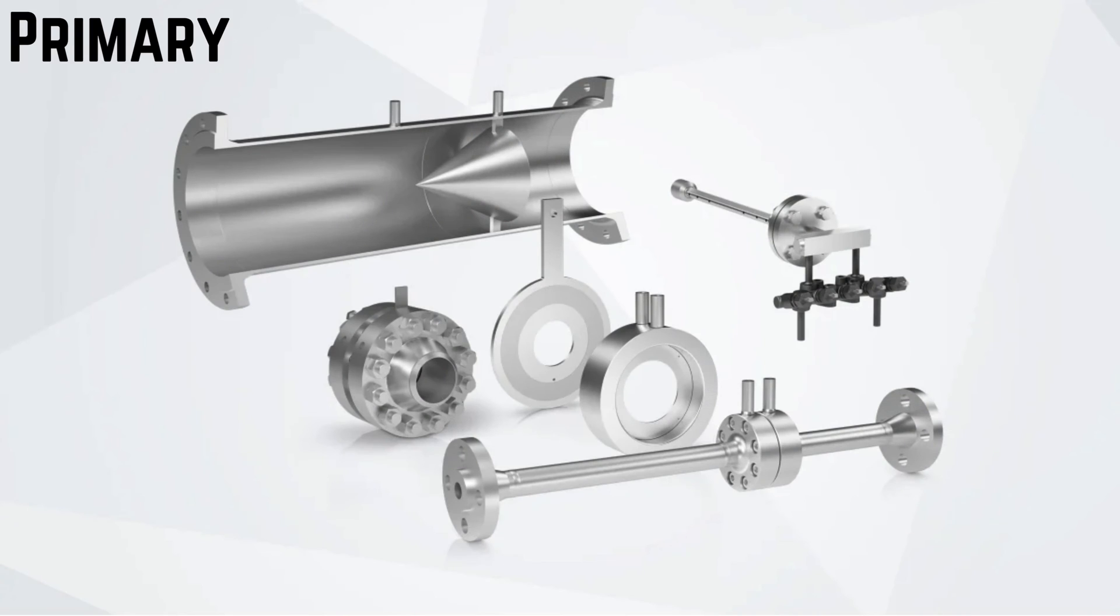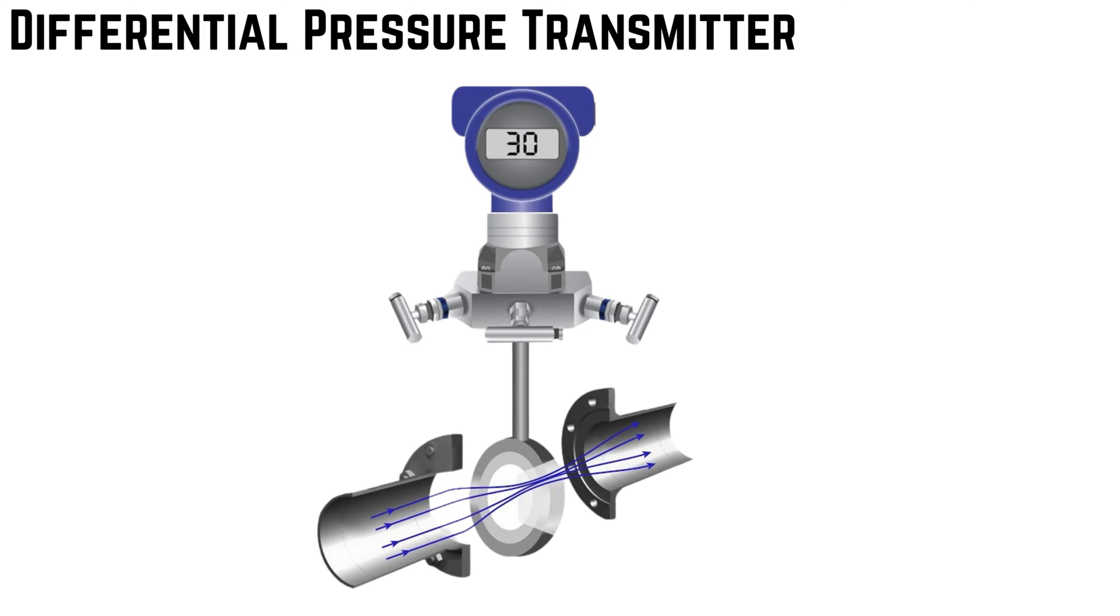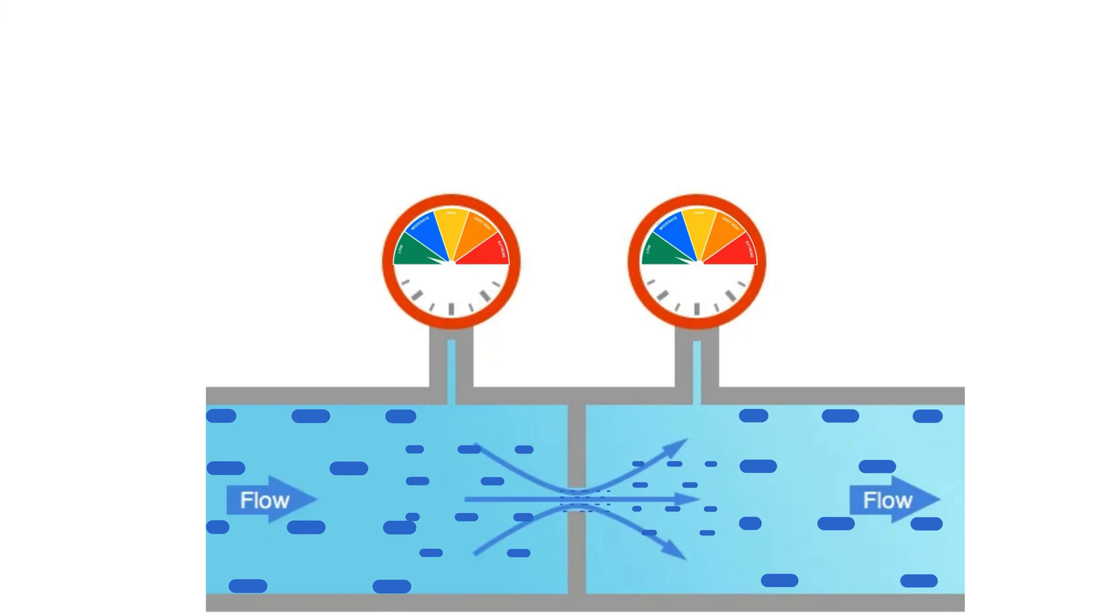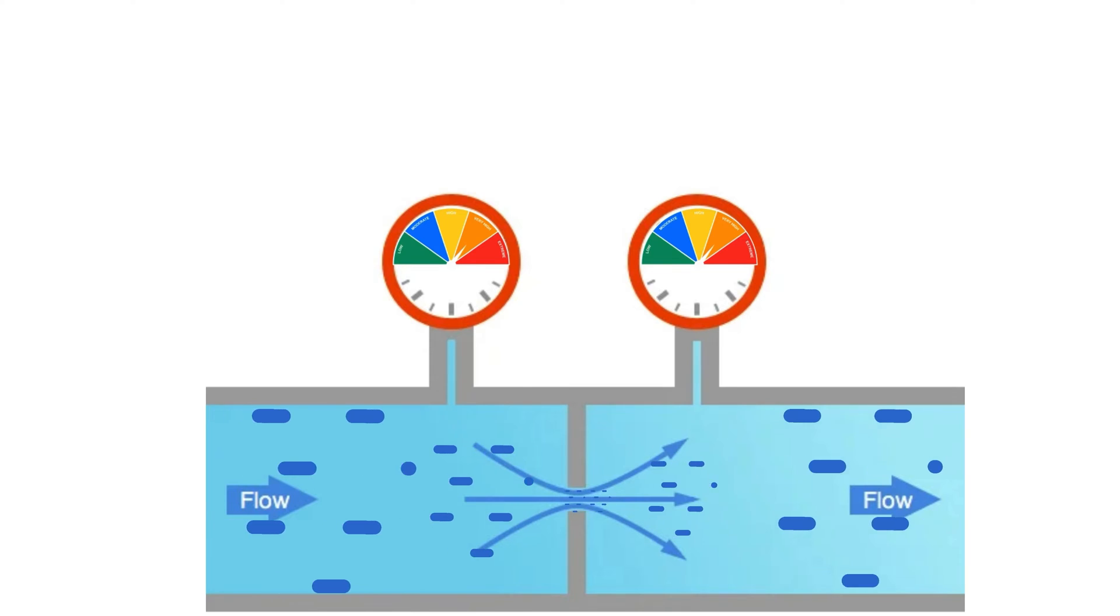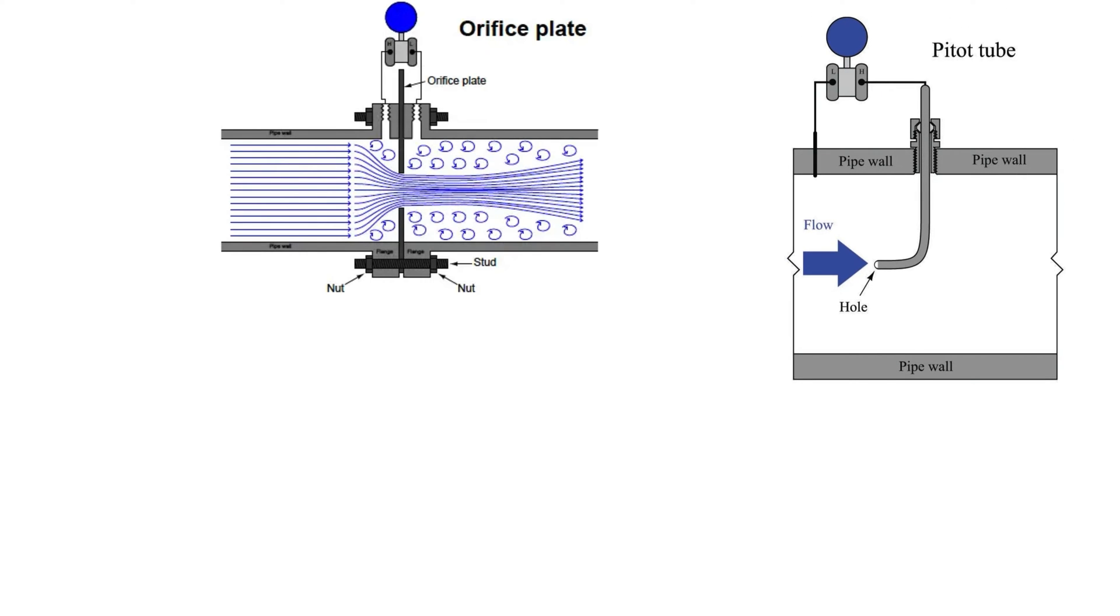This kind of flow meter consists of two parts: the primary element and the differential pressure transmitter. The DP flow meter will calculate the flow rate by measuring the differential pressure across a primary element. Various types of primary elements can be used to obtain differential pressure. Some of the most common primary elements are orifice plates, Pitot tubes, and venturi tubes.